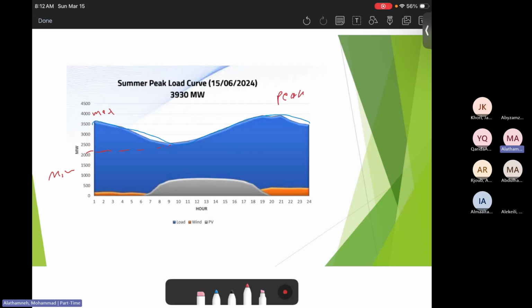When we look at the peak, we realize we cannot turn on all generation units at the same time because we don't want extra generation. If there's extra generation, the generators start to accelerate faster, and the frequency becomes unstable. Then we need to reduce the generation to make it stable. So during peak times...